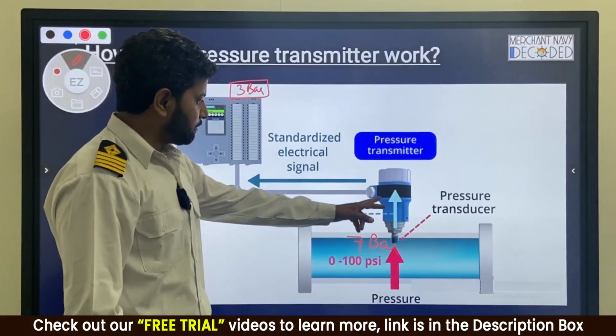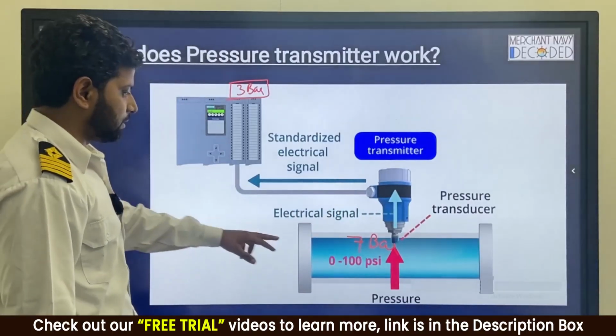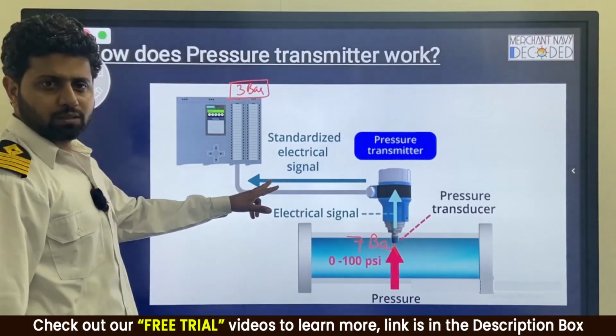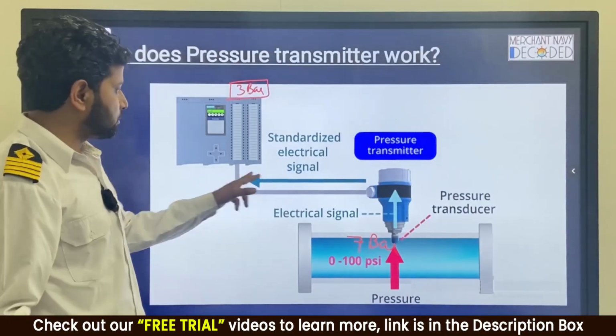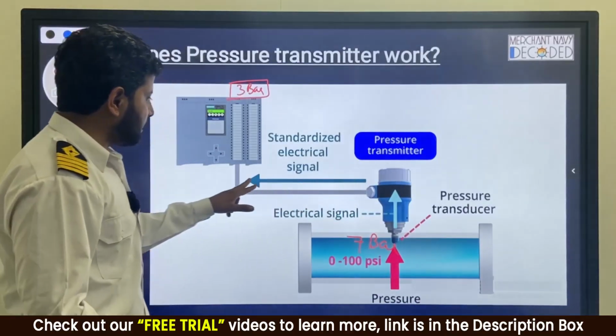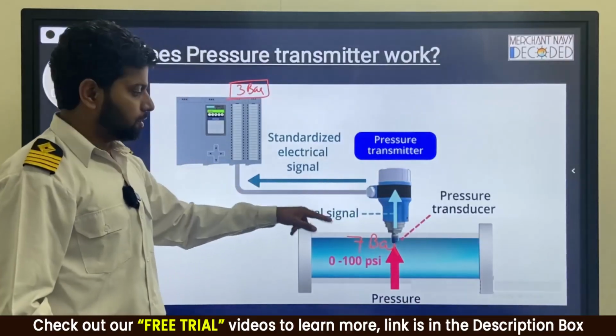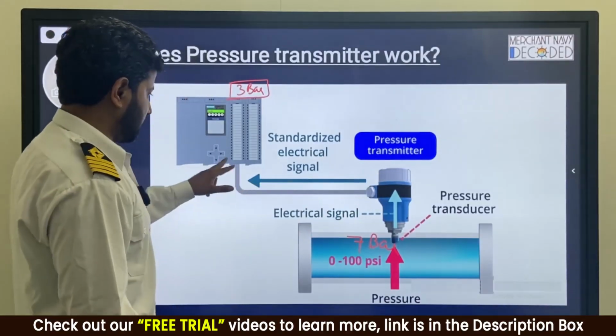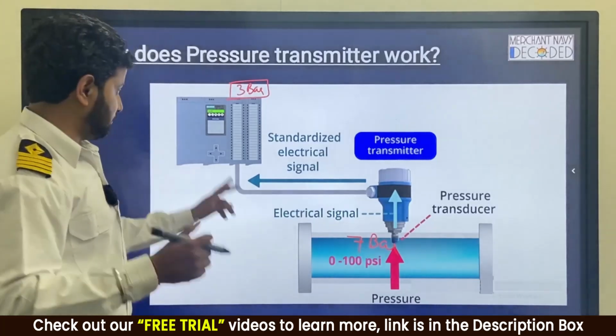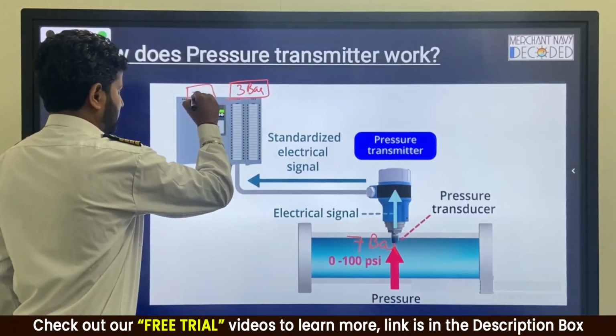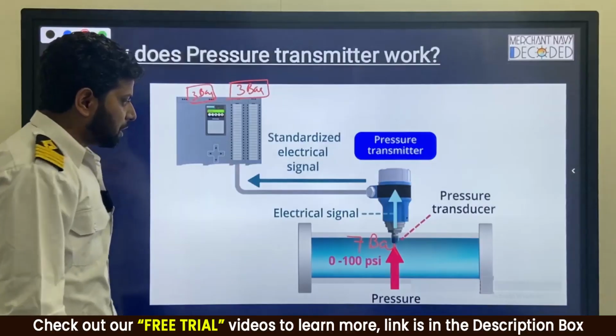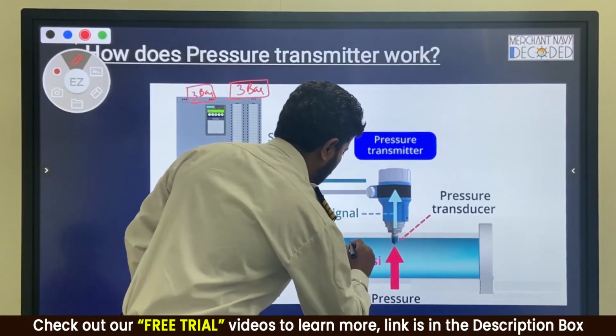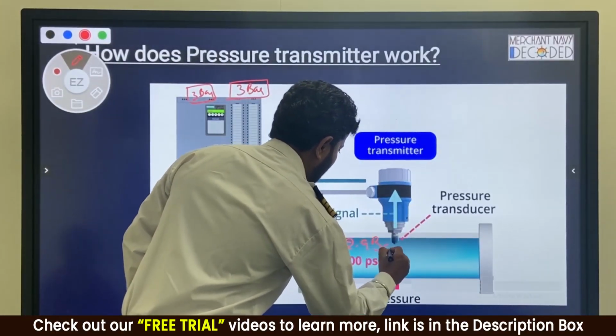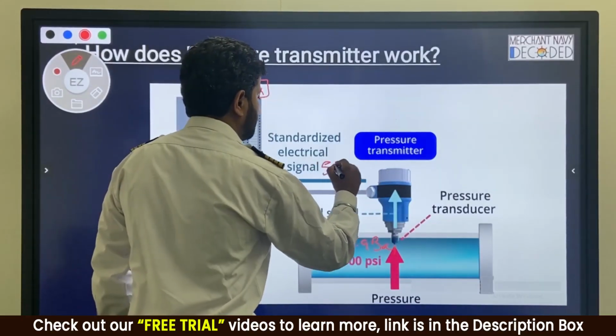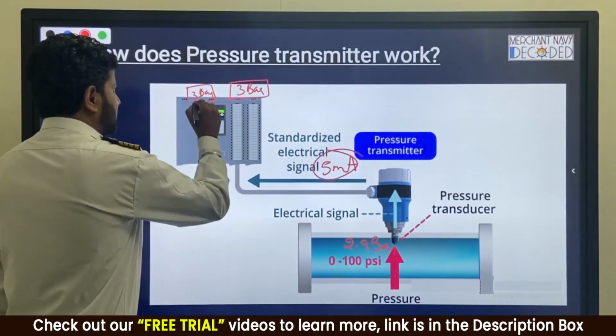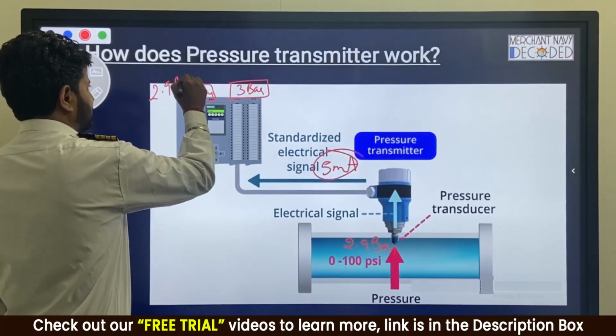So till the time it is 7 bar, it is sending 7 bar, 7 bar, 7 bar, 6 bar, the current signal reducing, say 18 milliamps, 14 milliamps, 6 bar, 6 bar, then 12 milliamps, when 5 bar, 4 bar, when it becomes 3 bar, the current signal becomes say 6 milliamps and it is showing 3 bar over here. Then also no problem. But now say the pressure becomes 2.9 bar over here. Milliamps over here is showing say 5 milliamps. This 5 milliamps reads 2.9 bar over here.